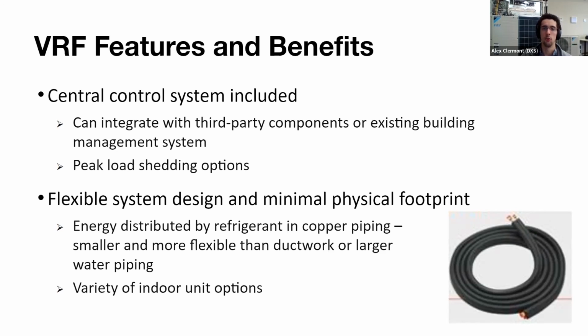Now, VRF systems also allow for great flexibility in the different kinds of indoor units, which Mike will go into in a little bit. But something important to remember is that VRF systems are zoning systems. So if you were to tell me, hey, Alex, I have a large warehouse, can I use VRF? You might be able to, but it might not be your best option. A packaged air source heat pump rooftop unit might be a little bit better for that warehouse. And again, VRF is all about smaller fan coils serving smaller zones.